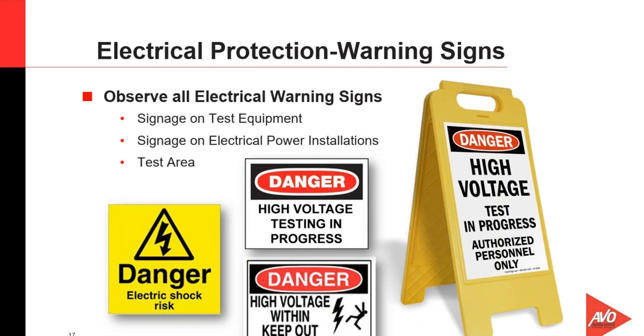Warning signs involve permanent labeling or fixed labeling out in the test area. We may have warning signs on test equipment. The manufacturers may have placed warning signs there as well. These need to be observed. An example here is danger, high voltage testing in progress. Electrical shock is imminent danger. Imminent danger signs typically are red, white, and black.